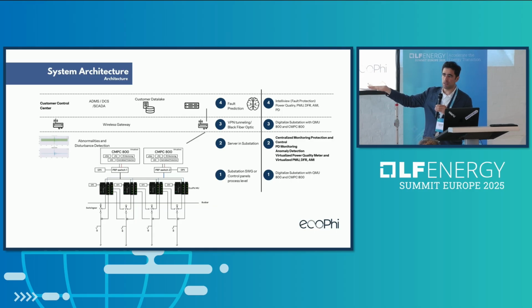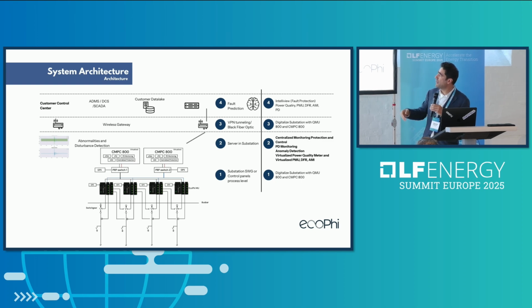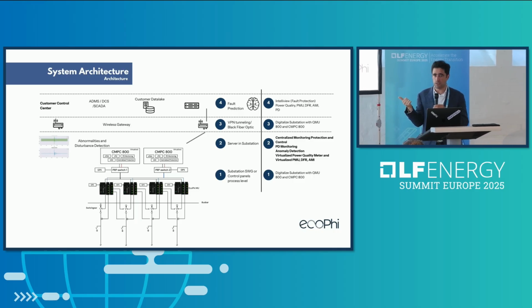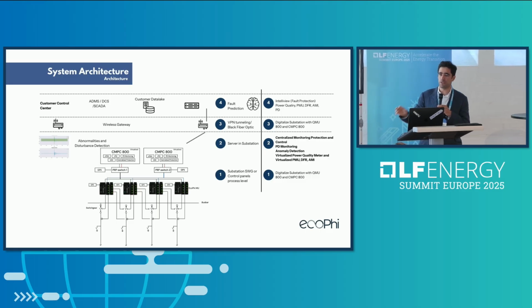You don't need to buy GPS separately. It can publish timestamps according to the IEEE 1588 version 2 PTP protocol, and go directly through the switch to the CMPC 800, the hardware shown earlier. There we deploy everything at the edge: virtualized PMU for phasor measurement, power quality according to IEC standard class A, PD monitoring, DFR system, and other applications, such as centralized protection from other vendors if needed.